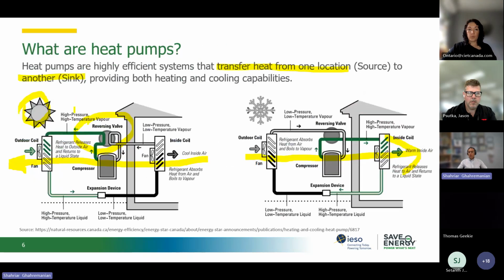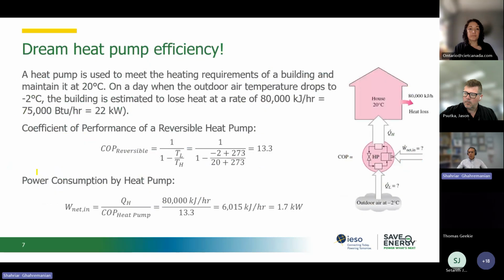Before jumping to that one, the other typical components of a heat pump are a compressor, an indoor coil or heat exchanger, an outdoor coil or heat exchanger, and an expansion device. These are typical equipment that exist inside an air conditioning system, but the only difference is the reversing valve that I wanted to touch on. But let's look at the ideal case, which we are never going to achieve, but this is from an engineering perspective.